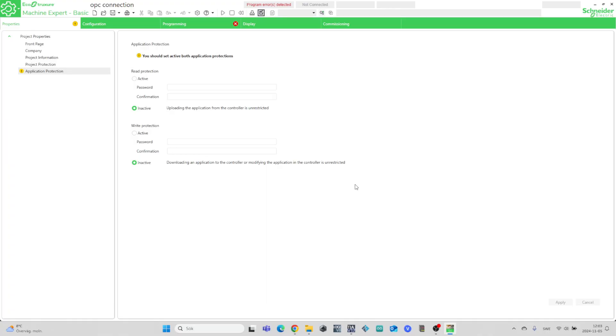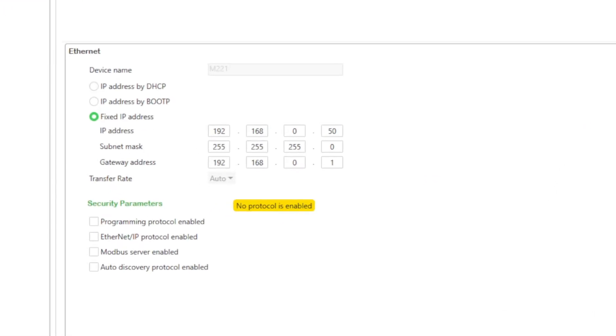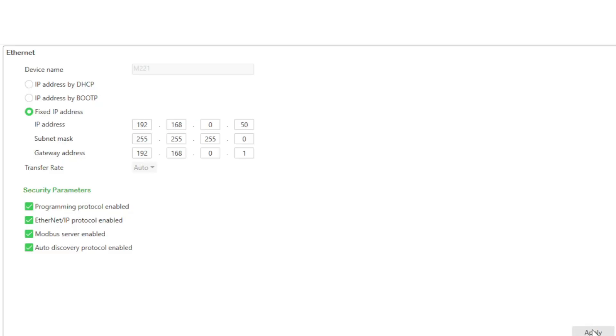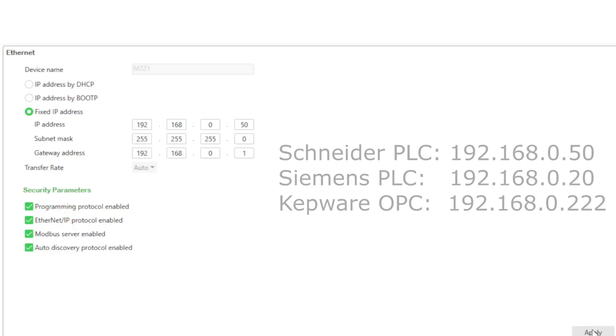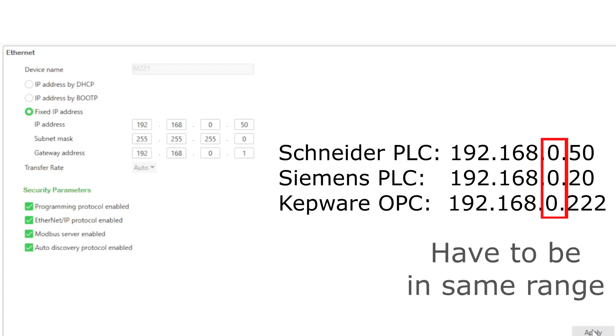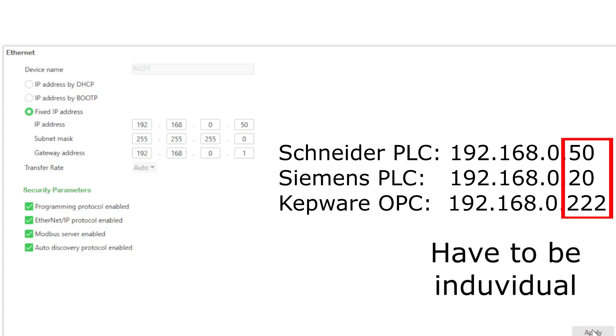In MachineExpert I will do the same steps as in TIA Portal. First we need to set an IP address and remove any possible security settings that can prevent communication. Make sure that all the IP addresses are in the same subnet range — this means the third parameter is the same, and the fourth has an individual number.